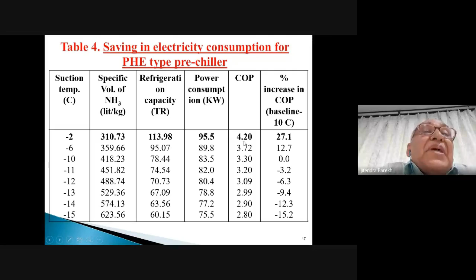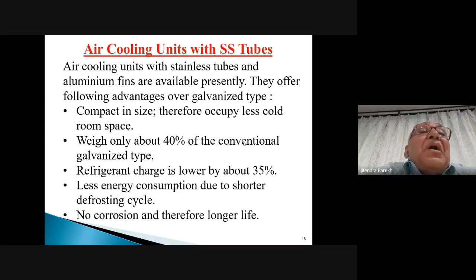We are also recommending air cooling units with SS tubes and aluminium fins, which are available presently. They offer the following advantages as compared to the galvanized type of tubes. Compact in design, thereby occupying less cold room space. Weight is only about 40% of the conventional galvanized type of tubes. Refrigerant charge is lower by about 35%. Less energy consumption due to the shorter defrosting cycle, no corrosion, and a longer shelf life. So the recommendation is that instead of galvanized tubes, we should use SS type tubes. Next, please.